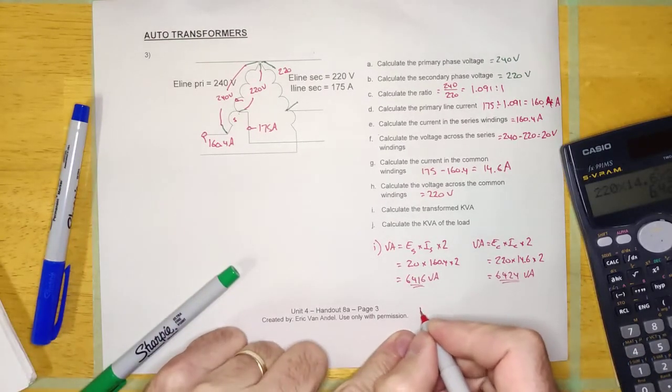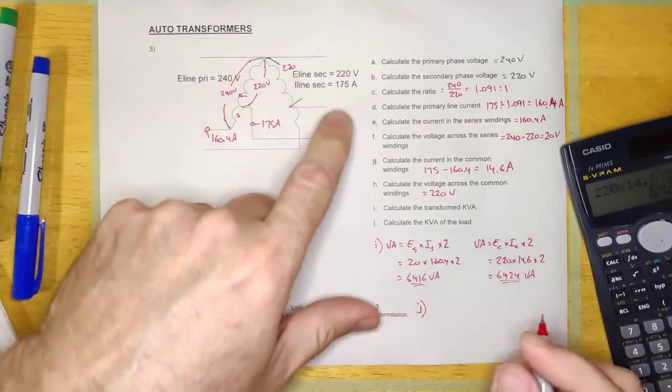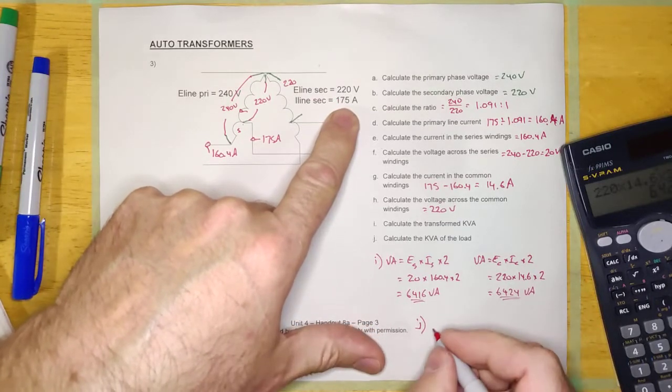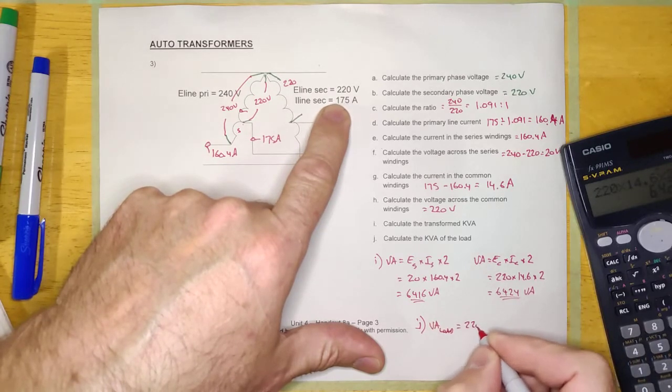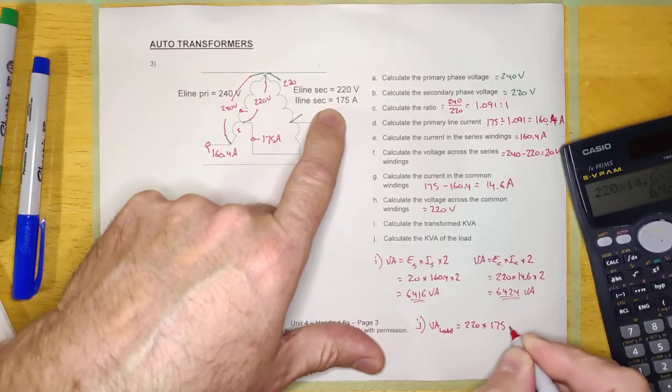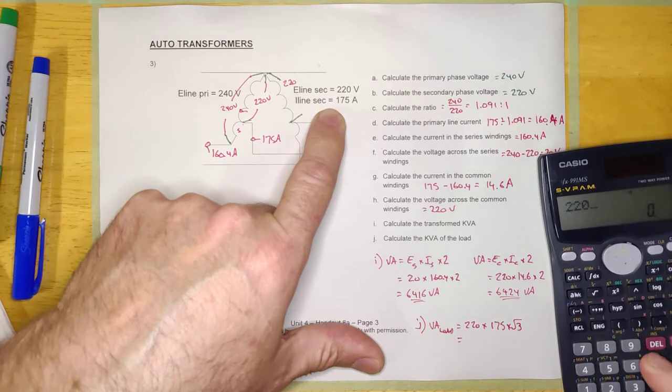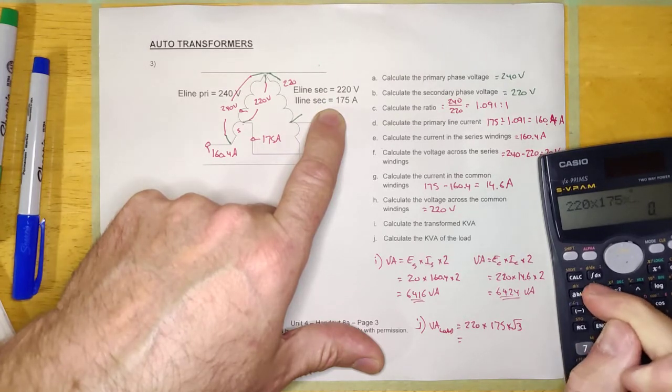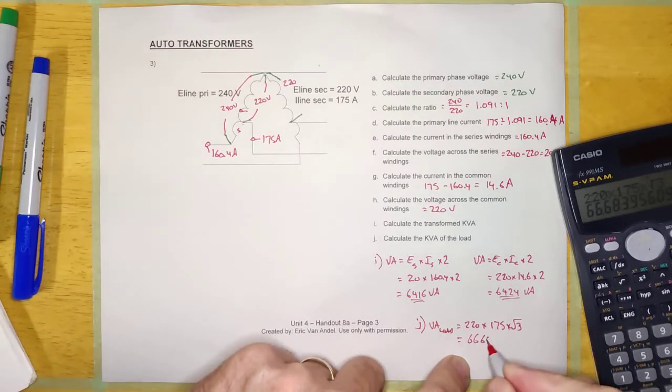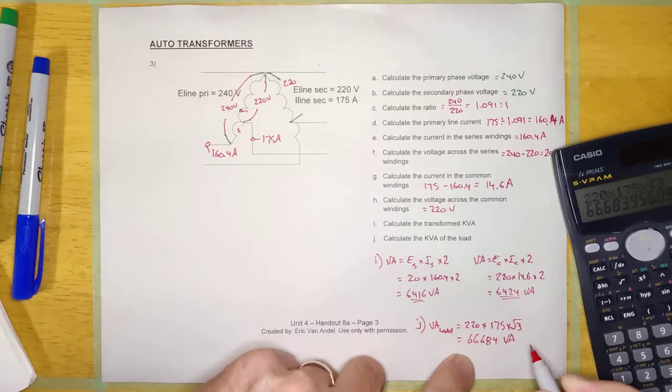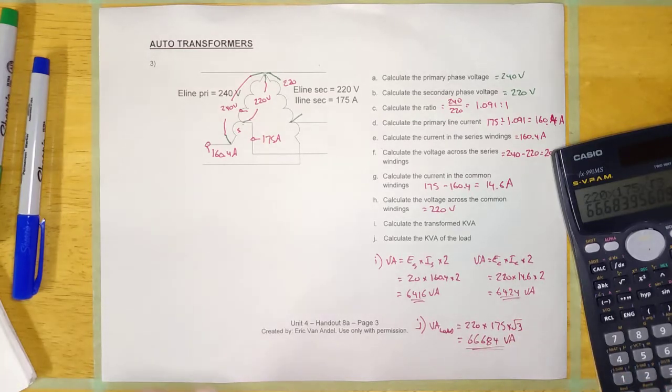Last question - calculate the kVA of the load. I don't know anything about the kVA of the load, but I know it's three phase, so I'm going to calculate it E-line, I-line, root 3. So the VA of the load will be E-line, 220 volts, times I-line, 175 amps, times root 3, because that's a three phase load. 220 times 175 times root 3, 66,684 VA. And again, massive load made out of a tiny transformer.